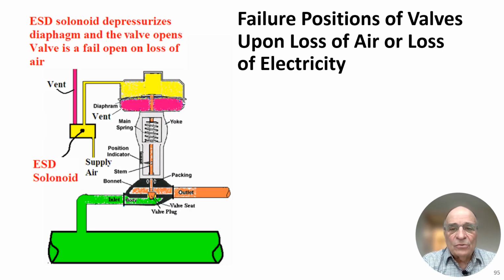This picture is shown just to let you know that there are failure modes for valves. In other words, if you have a loss of air or a loss of electricity to the ESD solenoid associated with that valve, the valve will fail in a certain position. That valve can be a fail open, could be a fail closed, could be a fail as is, could be a fail at a fixed position, whatever the design engineer designs it to be. But operators and engineers should be aware that all of the automated valves in the plant have fail type positions: fail open, fail closed, fail as is, etc.